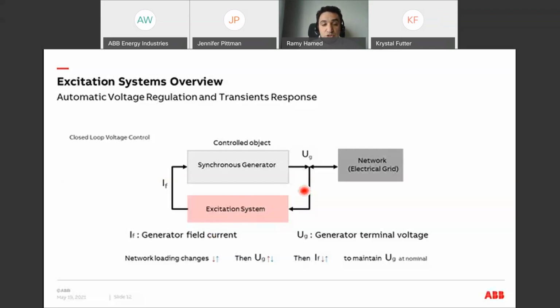But instead of the temperature, the excitation system is trying to maintain the generator voltage at its nominal value. Here we might ask a couple of questions. First, why do we need to maintain the generator voltage at its nominal value? So we need to maintain the generator voltage at its nominal value, not to damage the network. If the voltage in your home is far from 110 or 220, most of the appliances will be damaged. The second question would be why the generator terminal voltage is changing. Simply because the network loading is changing all the time.